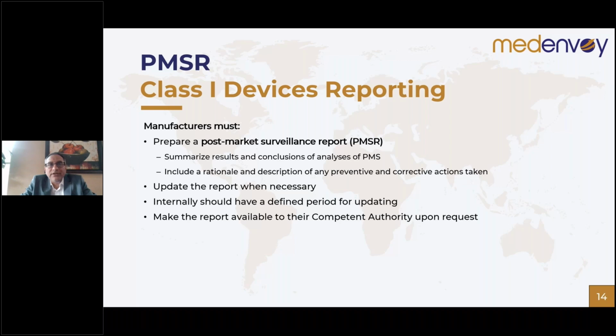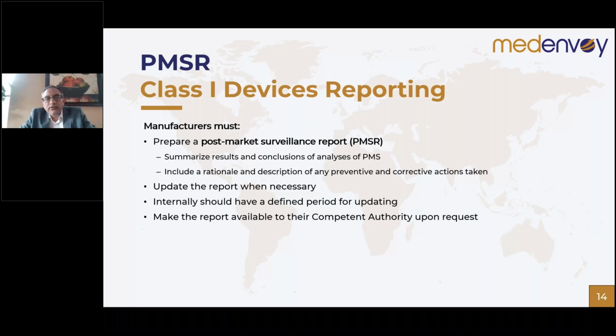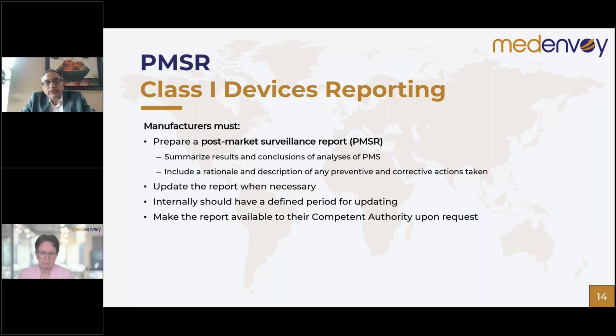For example, if you have a significant change, design change, or any change, you update the post-market surveillance report, or you define the frequency. You define, as a manufacturer, what should trigger an update. You could say, I'll update every year, or every 2 years. There is no mandatory time requirement in the regulations, but it should be defined. So if you have not defined that frequency in your procedure, that is a non-conformance from a notified body perspective.